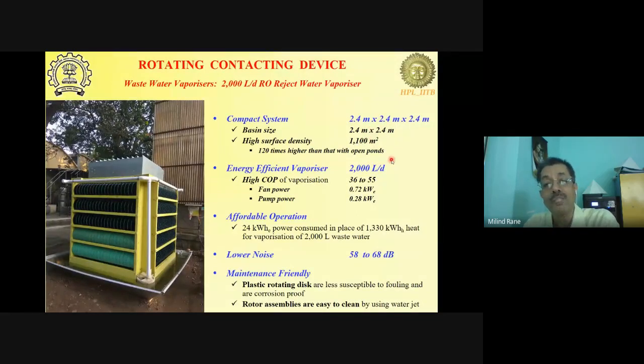Okay. So the enhancement in the surface area offered, compared to an open pond, a solar pond often used for vaporizing wastewater, was around 120 times in this particular example. Okay. And the fan power was only 0.72 kilowatt and the pump power was only 280 watts. So the total power consumed was around 1 kilowatt, and we are vaporizing a very large amount of water during the day.